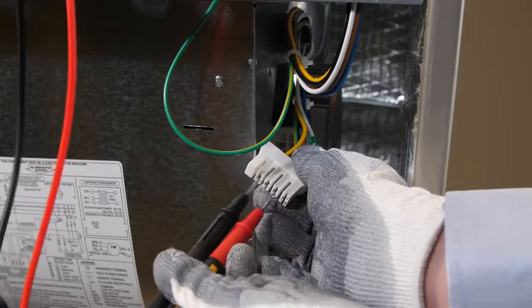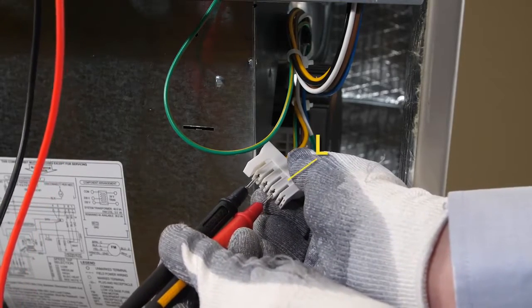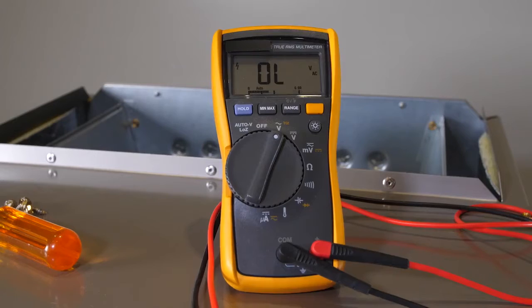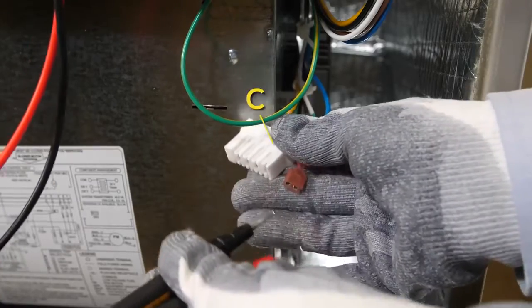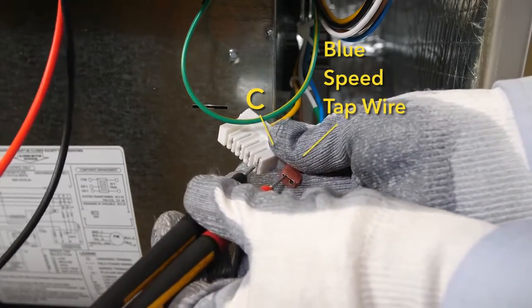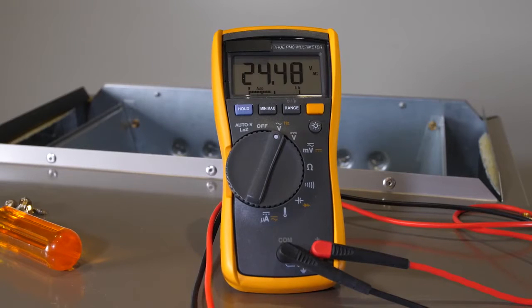Using a voltmeter, check for proper high voltage at the L, G and N connections at the harness. Voltage should read between 208 and 230. Check low voltage power between C on the white plug and the blue speed tap wire. Confirm that you have 24 volts AC.